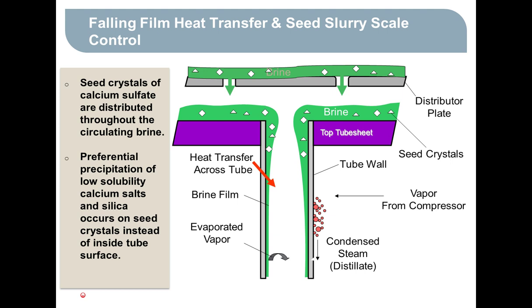And out on the outside of the tube, vapor, which came from the compressor, condenses on the outside of the tube and gives up its latent heat, which transfers across the tube wall and causes the film on the inside of the tube to boil. And the vapor flows in the same direction down the tube along with the liquid to the bottom of the tube, and at that bottom vapor body, that's where the separation of the vapor and liquid take place.